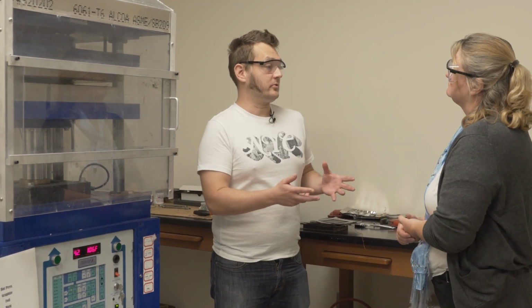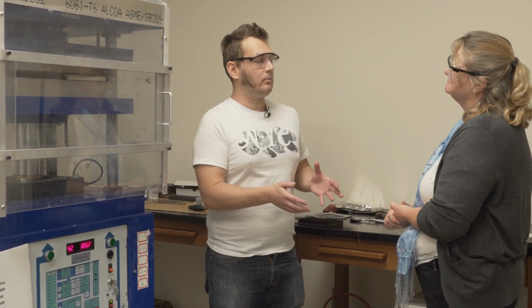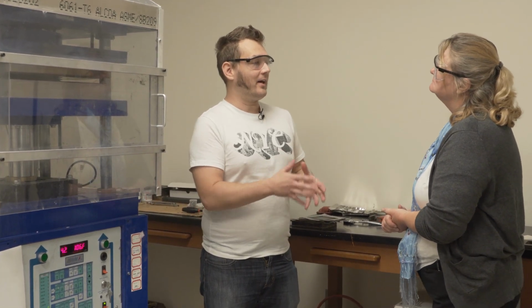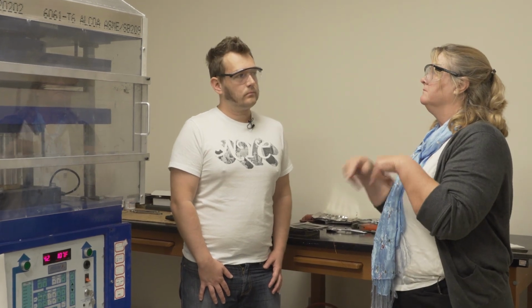So how do you deal with the fact that you've got a potentially flammable liquid like methanol in the pores of the gel, inside a hot press that has to be sealed? How do you manage that without an explosion hazard? Right, so there's a small amount of methanol — it's not as if we have an autoclave-sized pressure vessel full of it. What we do is use a safety shield on the hot press, and there's a little bit of flow when we release, so we capture that gas. Scaling up, that's going to be a bigger issue, but for the small sizes we have, we've never had a problem with that.